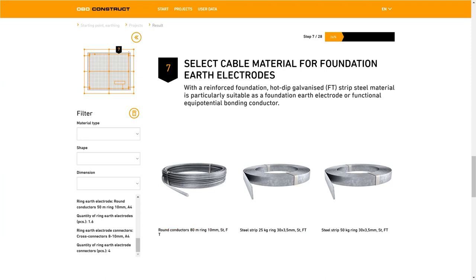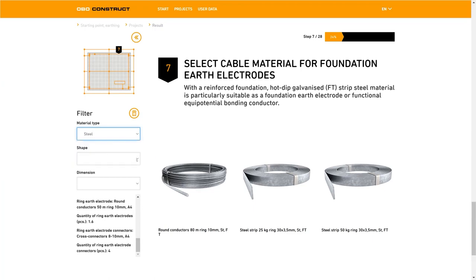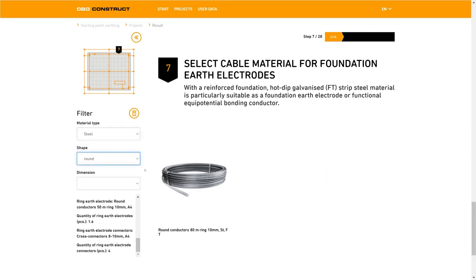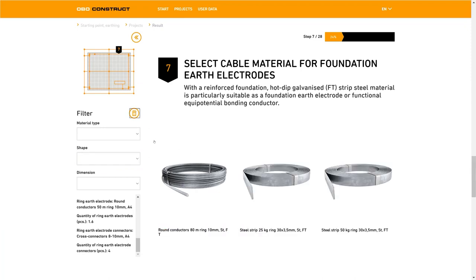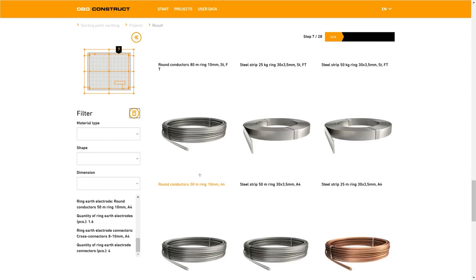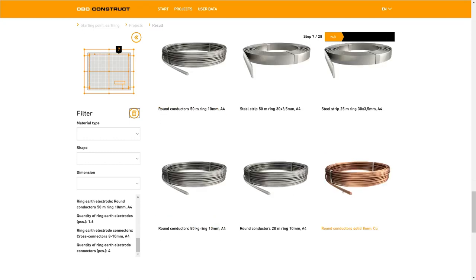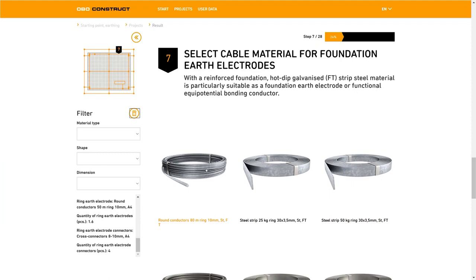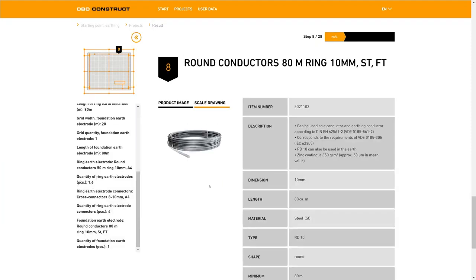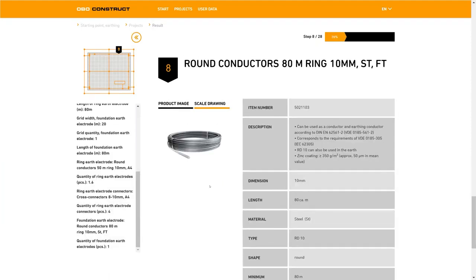As you can see step 7 is again displayed in our sketch. We're now in the floor plate in the concrete itself. It's possible to use filters here directly, for example by saying that we want to use steel in a round form. At this point the only ring earth electrode possible appears. But we also have the option to see our complete selection - a useful way to check things if you're uncertain about any aspect. You could also select copper, but we'll stick with the round conductor in a material thickness of 10 millimeters.